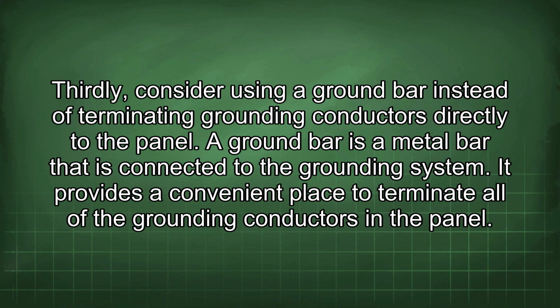Thirdly, consider using a ground bar instead of terminating grounding conductors directly to the panel. A ground bar is a metal bar that is connected to the grounding system. It provides a convenient place to terminate all of the grounding conductors in the panel.